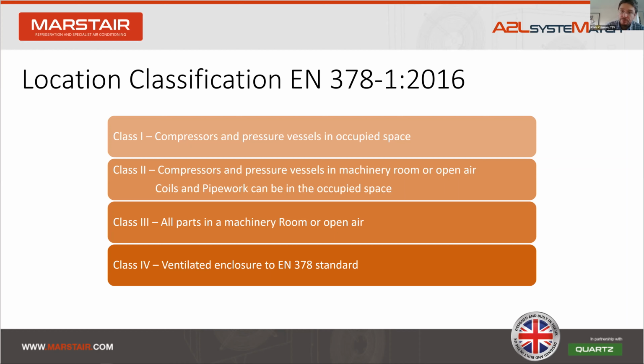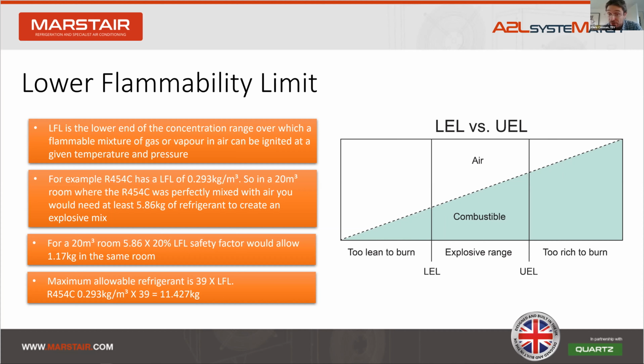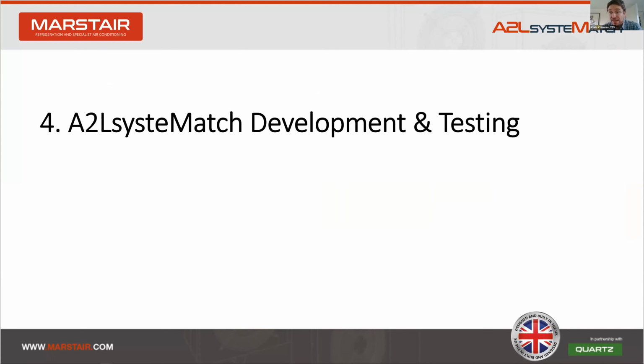This calculates to only allowing 1.17 kilograms of R454C in a 20 cubic meter room, which I can tell you is not a lot of refrigerant. The maximum allowable refrigerant for a split system, 39 times the LFL, actually equates to 11.4 kilograms once you go to as big a room as you can get. So, developing the testing, what have we done in terms of developing our new A2L split system product?